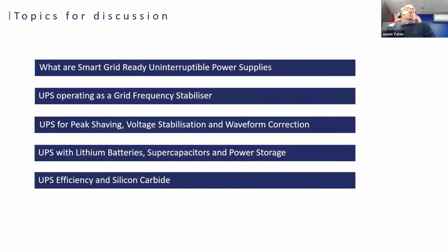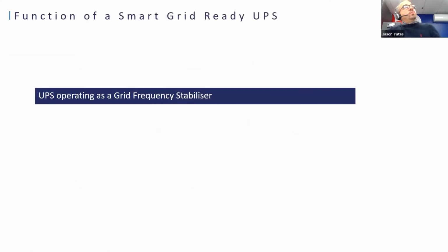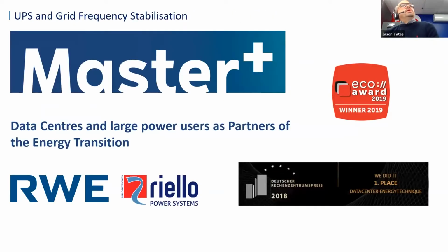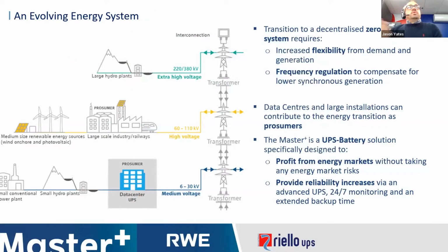So just to show you one of the projects that we did, this was a project for a grid frequency stabilizer. This project was done in conjunction with RWE. The brief for this project was to enable data centers and large power users to become partners of the energy transition. Obviously, transition to a decentralized zero carbon system requires increased flexibility from demand and generation, along with frequency regulation to compensate for low synchronous generation. Data centers and large installations can contribute to the energy transition as prosumers.